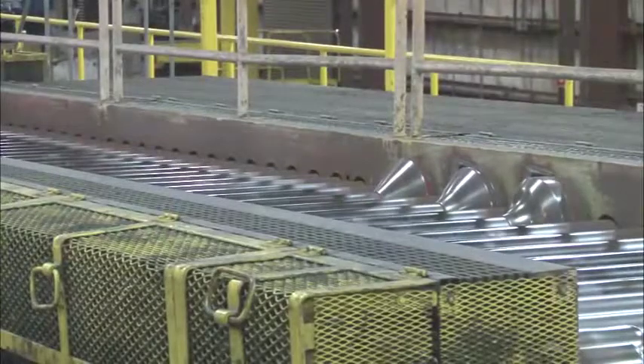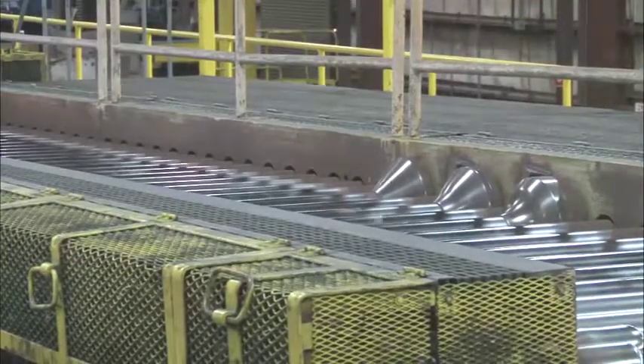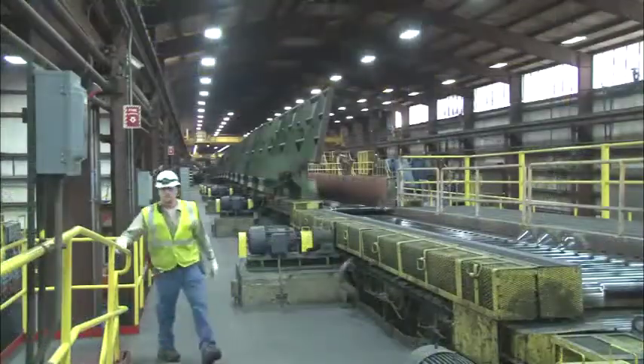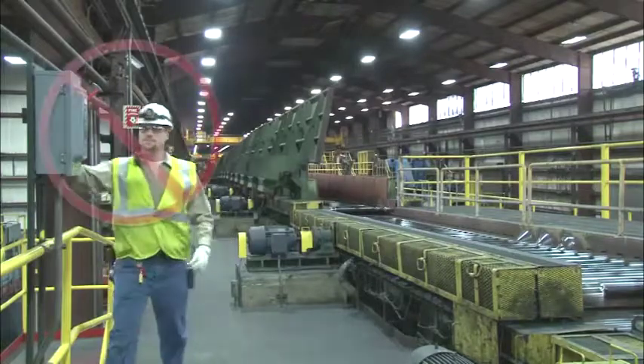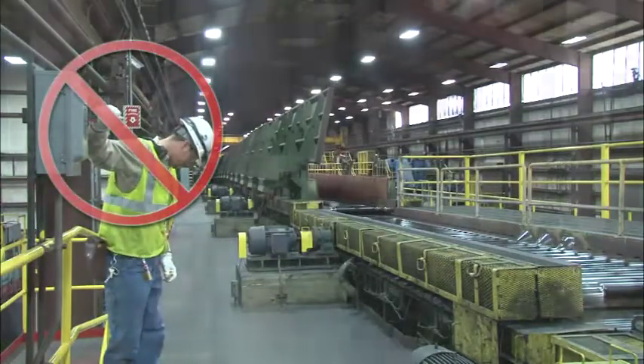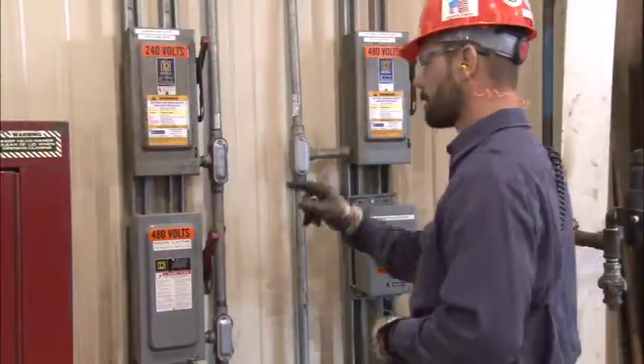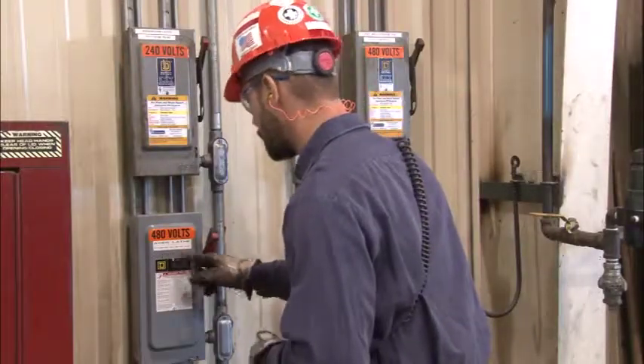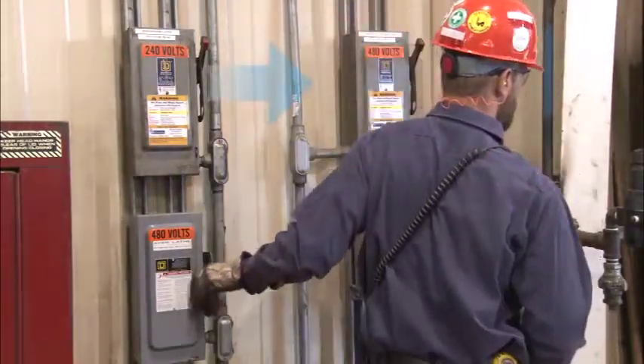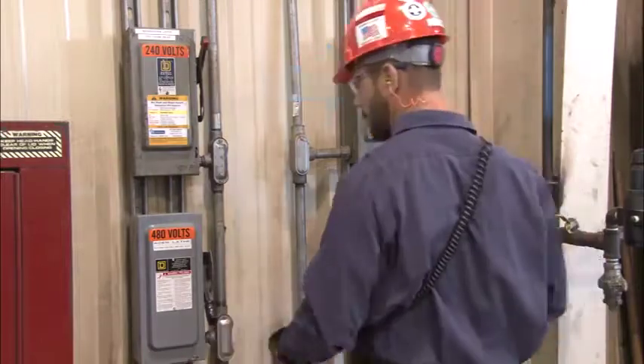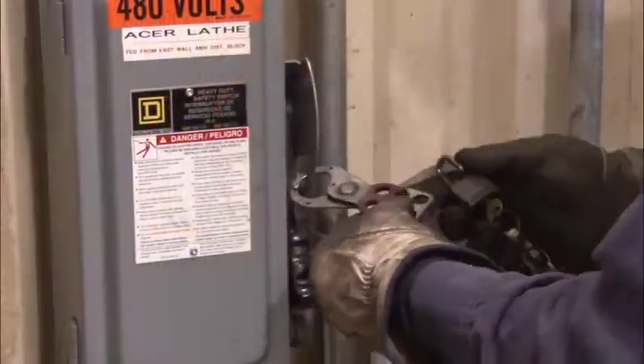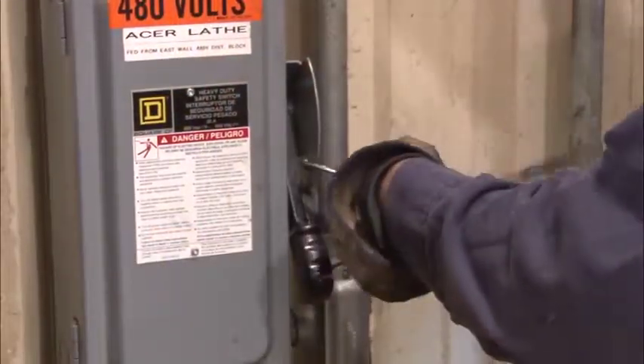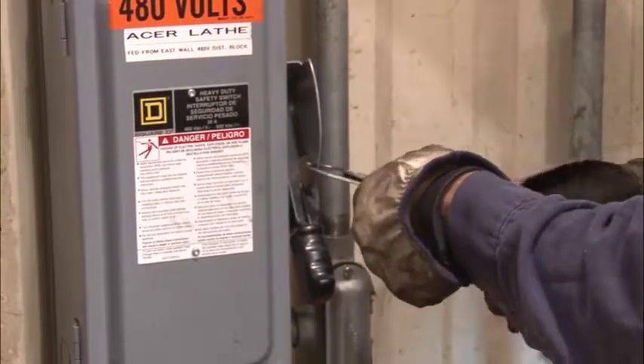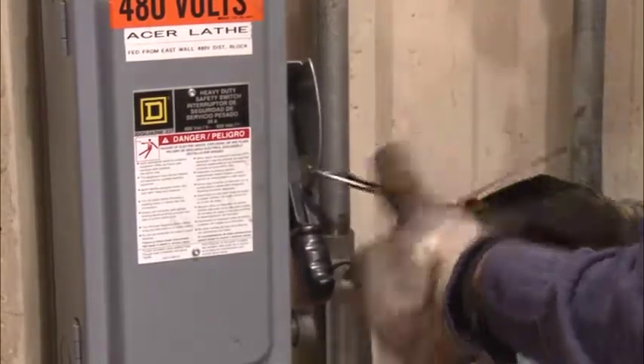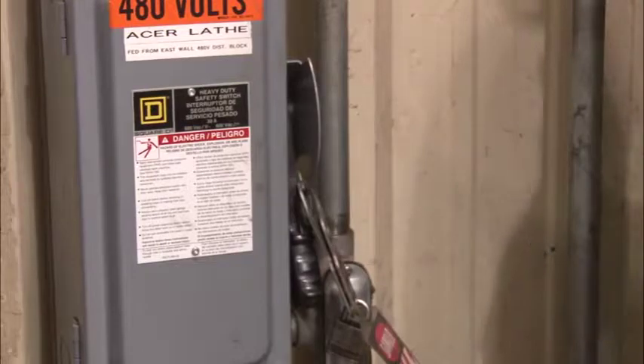It is important to note that electrical disconnects must never be pulled while equipment is still operational due to the potential for a dangerous arc flash event to occur. In addition, electrical disconnects should only be pulled while standing off to the side with your head turned away while wearing the appropriate PPE. With the energy isolating devices in the safe or off position, locks are then placed on the energy isolating devices so they cannot be removed or activated.